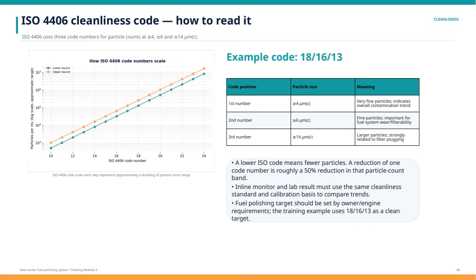This standard uses 3 code numbers that correspond to particle counts at sizes of 4 micrometers, 6 micrometers, and 14 micrometers. These 3 numbers provide insight into different ranges of contamination. The first number, representing particles equal to or larger than 4 micrometers, indicates very fine particles and gives a general sense of the overall contamination trend. The second number, for particles 6 micrometers and above, reflects fine particles that are crucial because they can affect fuel system wear and filterability. The third number corresponds to larger particles, 14 micrometers and larger, which are strongly associated with filter clogging. The code scale works by doubling the particle count with each one-step increase.